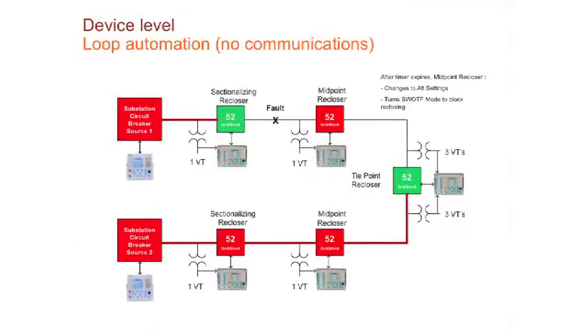So once the fault happens here, obviously this sectionalizing recloser will go through the 3 or 4 shots that you've programmed it to. So you have 1, 2, 3, let's say 4 shots to lockout. After the 4th shot, it goes to lockout, and the PT or VT on the midpoint recloser senses the loss of voltage. That kicks off a timer. All these devices have timers, and you pre-configure them before you deploy. I think you can go to the next one. After the timer expires, it changes to alternate settings, and it turns on a function that blocks reclosing.